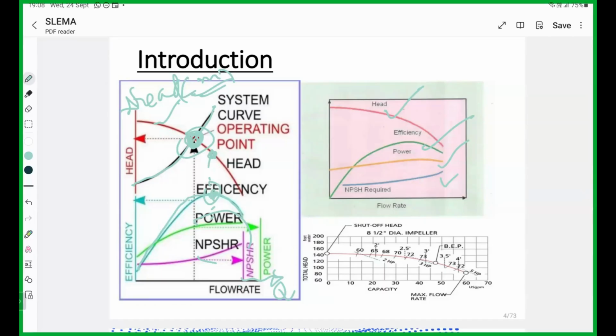You have to have an understanding of this before thinking about energy conservation. It is very important when you are going to select a pump. NPSHR is a very important one, but we are not going to cover it in this session. You have to keep in mind that these are also important, right? If you think about the pump curve, this is called the shut-off head, then the best efficiency point, and the maximum flow rate we normally call the run-out point, right? We have this sort of thing in a pumping system.